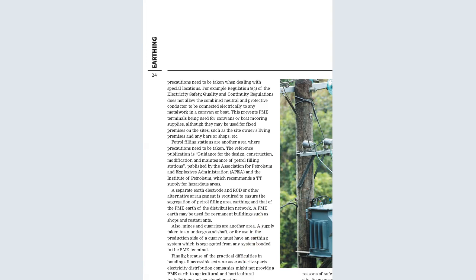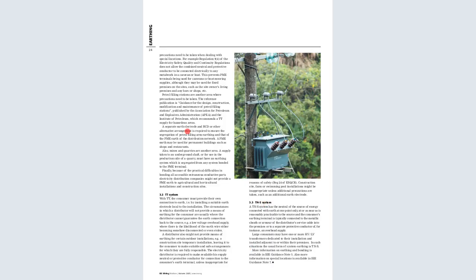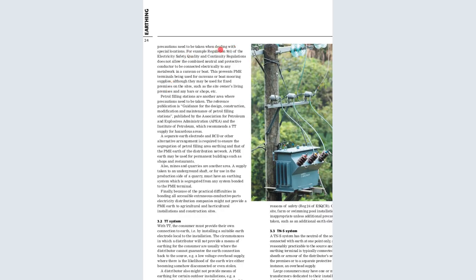So the Kenya Power normally uses the PME. Now, precautions need to be taken when dealing with special locations. For example, the electrical safety, quality, and continuity regulations do not allow the combined neutral and protective conductor to be connected electrically to any metalwork in the caravan or boat. So this prevents the PME terminals being used for caravans or boat mooring supplies, although they may be used for fixed premises and sites.